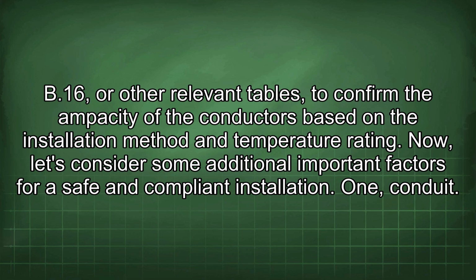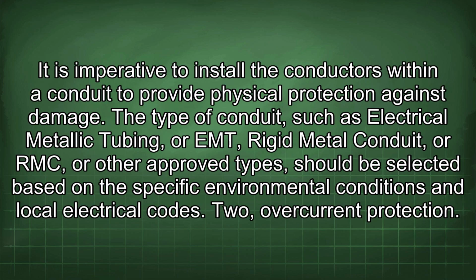Now let's consider some additional important factors for a safe and compliant installation. 1. Conduit. It is imperative to install the conductors within a conduit to provide physical protection against damage. The type of conduit, such as electrical metallic tubing, or EMT, rigid metal conduit, or RMC, or other approved types, should be selected based on the specific environmental conditions and local electrical codes.